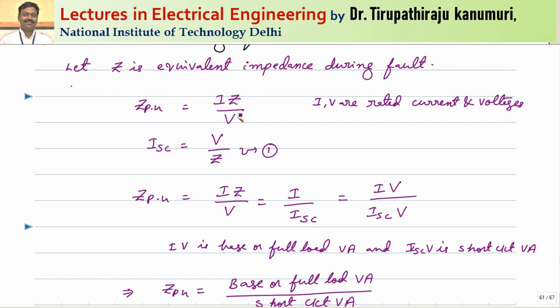Z per unit can be calculated as Z divided by Z base. Z base is nothing but voltage base divided by current base. Alternatively, Z per unit can be represented as I·Z divided by V, where I and V are the rated current and voltage. The short circuit current ISC equals the source voltage divided by the impedance up to the fault.